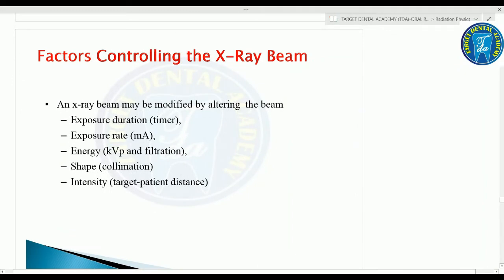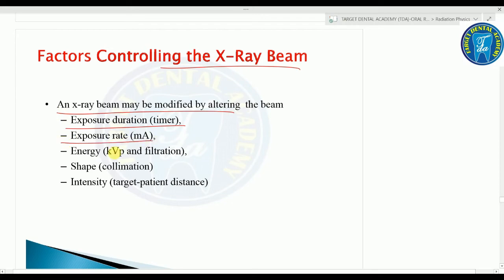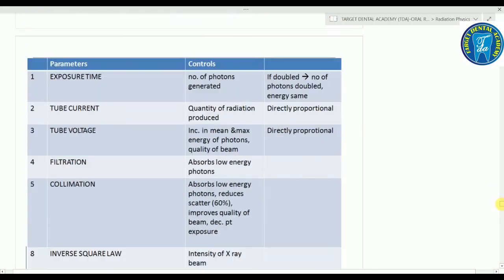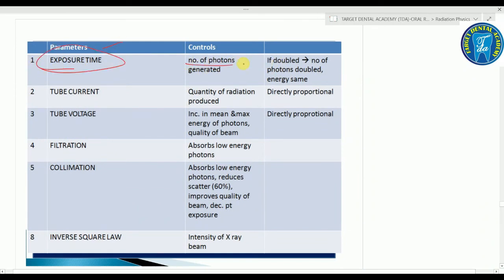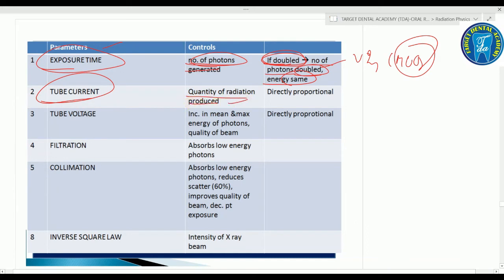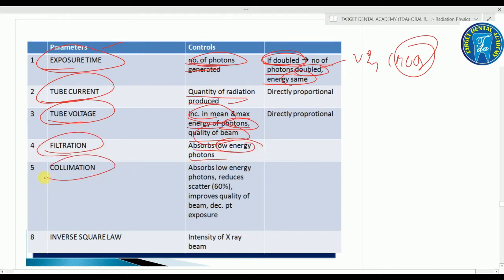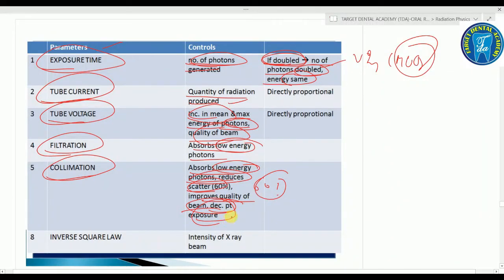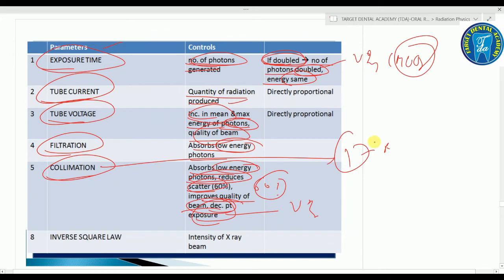Factors controlling the X-ray beam: exposure time controls the number of photons generated — when exposure time doubles, the number of photons also doubles with the same energy. Tube current is directly proportional to the quantity of radiation produced. Tube voltage is directly proportional to the increase in mean and maximum photon energy. Filtration absorbs low energy photons. Collimation absorbs low energy photons, reduces scattered photons by 60%, improves image quality, decreases patient exposure — very important MCQ.